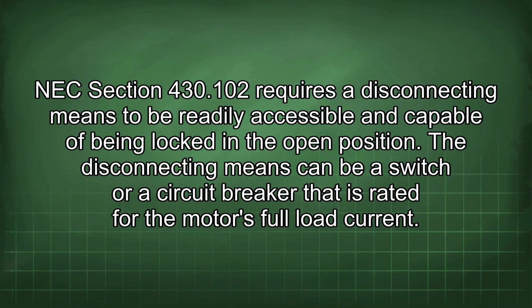430.102 requires a disconnecting means to be readily accessible and capable of being locked in the open position. The disconnecting means can be a switch or a circuit breaker that is rated for the motor's full load current.